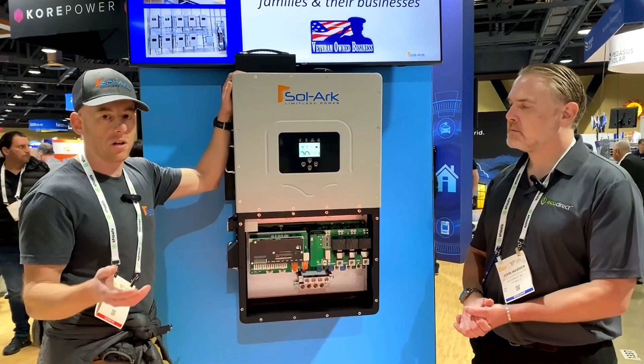Great question. To answer the first comment about lead acid, when working with this inverter - it's a medium to high voltage battery compatible inverter. That's different than our residential inverters, which are 48 volt nominal low voltage inverters. When working with a low voltage inverter, it's much easier to do open loop with lead acid or a battery that may be off-brand that doesn't already communicate with the Sol-Ark. However, when working with medium to high voltage batteries, for safety, you have to have a battery that can communicate with the inverter closed loop, and it needs a battery management system. So lead acid is probably not going to be an option, but with lithium, it would be a medium to high voltage option that would communicate with the Sol-Ark.